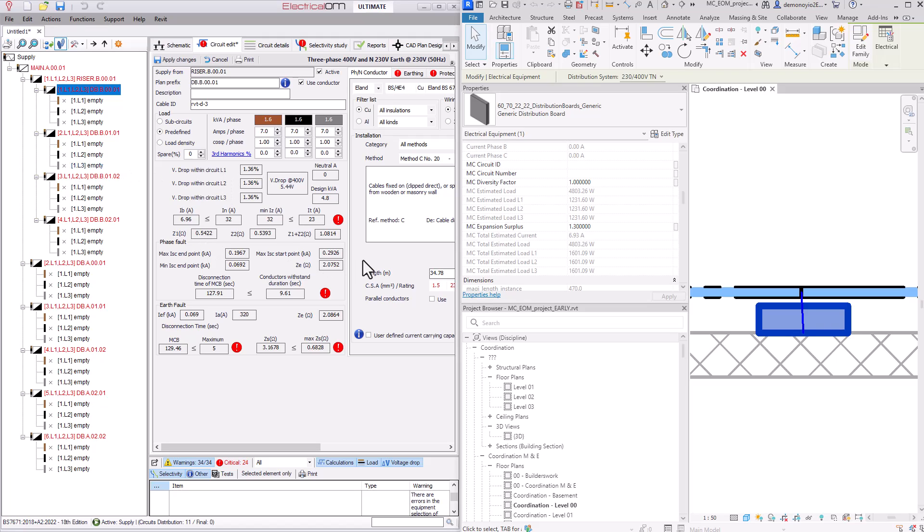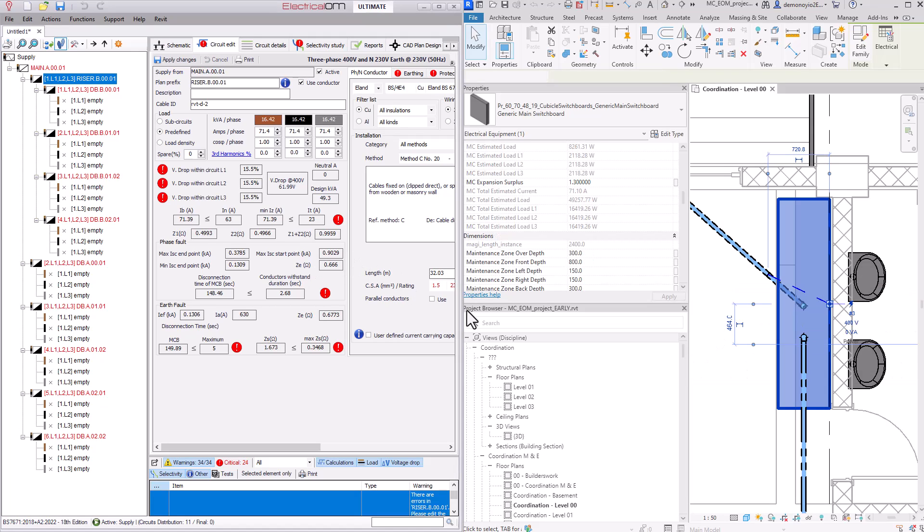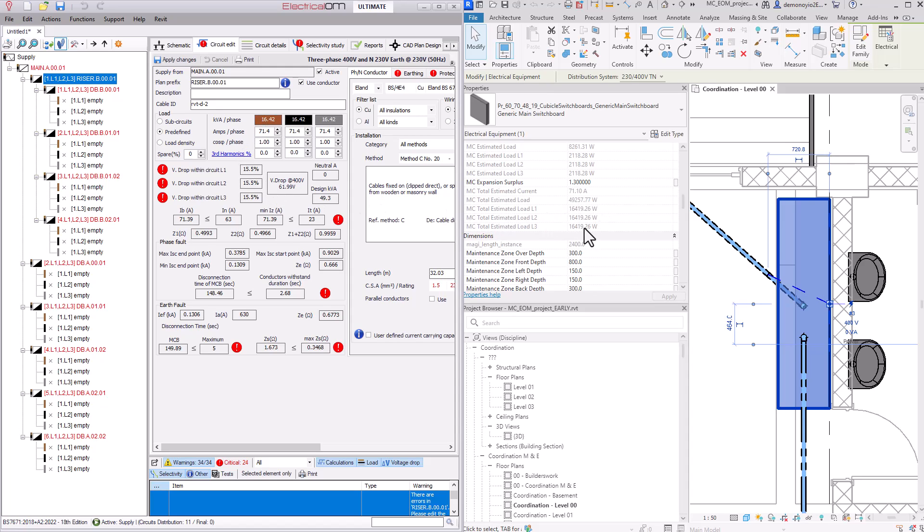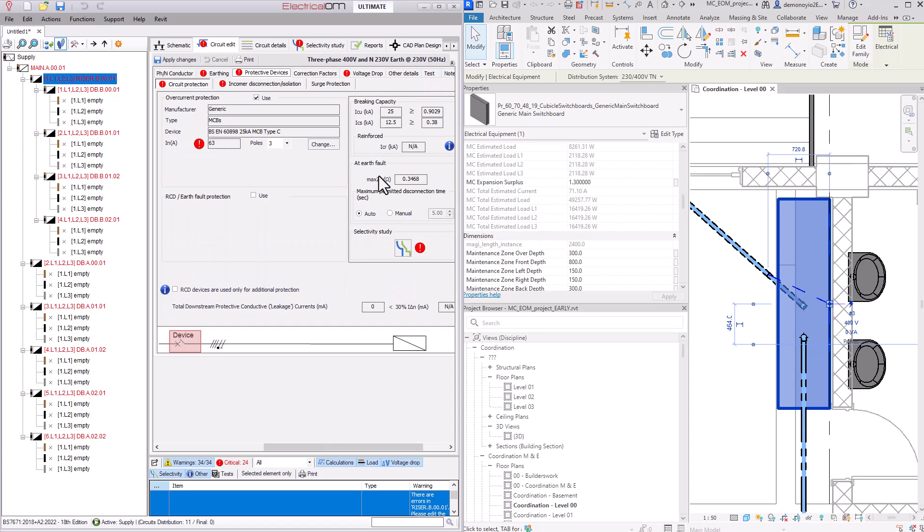If within electrical OM I need to make a change or add additional detail I can. For instance here we have a load on the switchboard and the load is currently at 71 amps based upon the data within MagiCAD. If we select the protected device the software has now identified that there are some compliance issues around this selected device that has been chosen within MagiCAD.